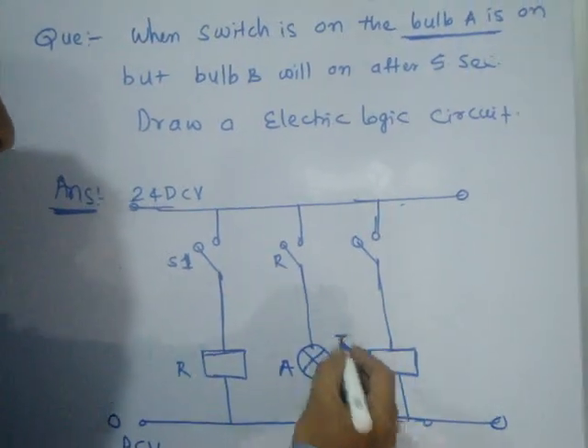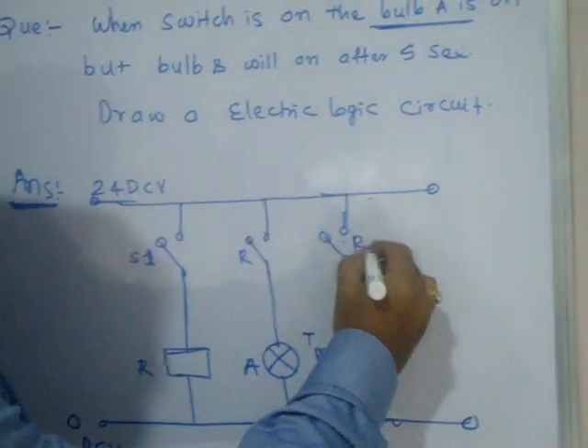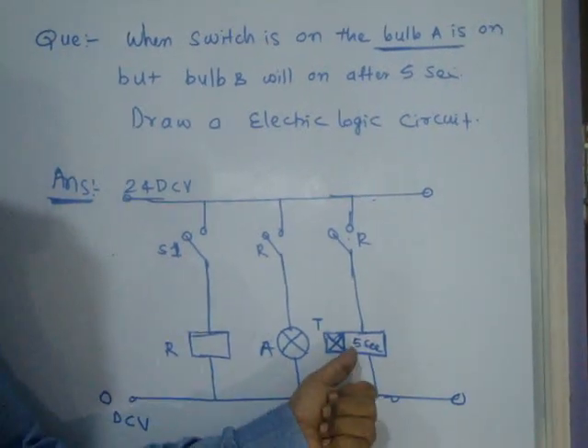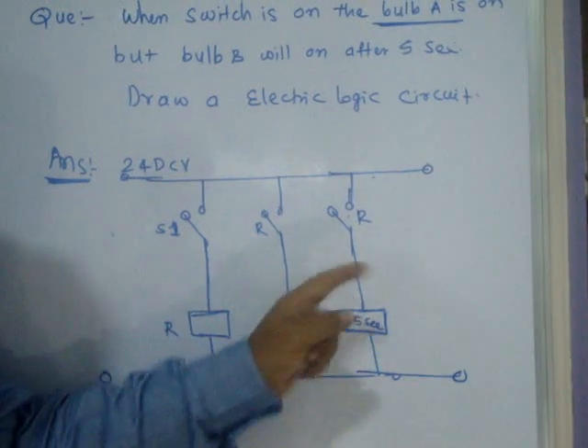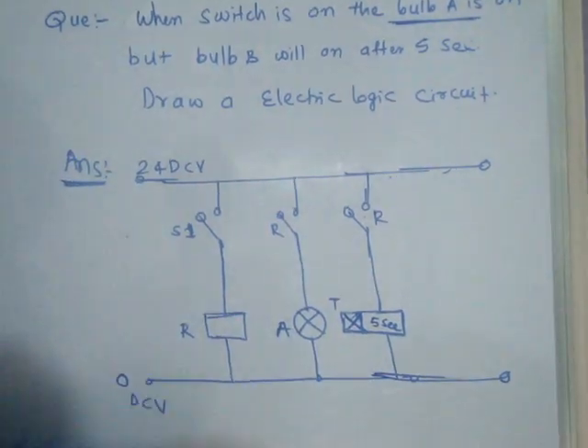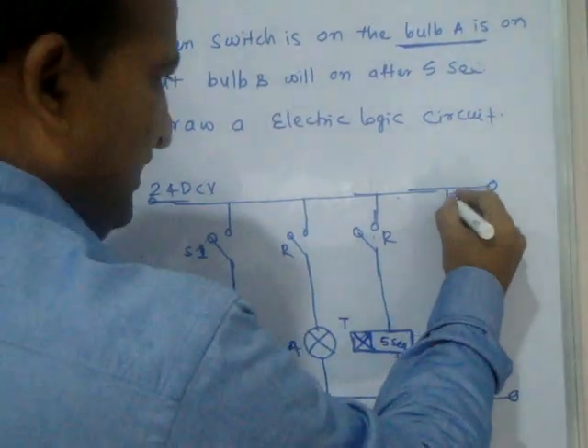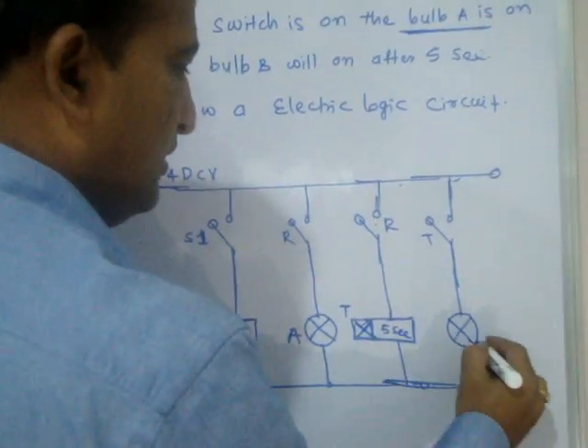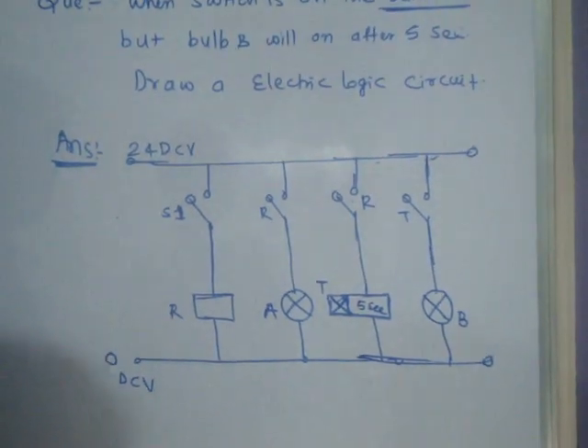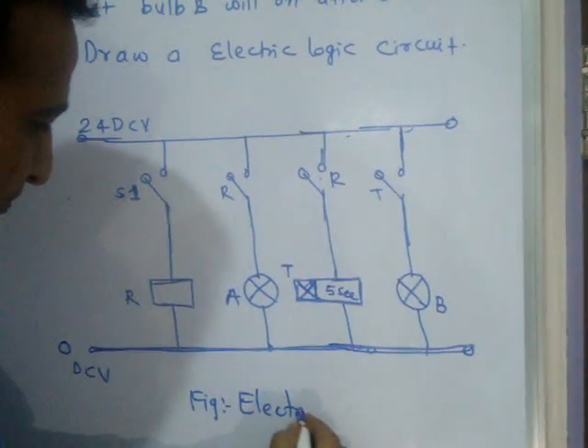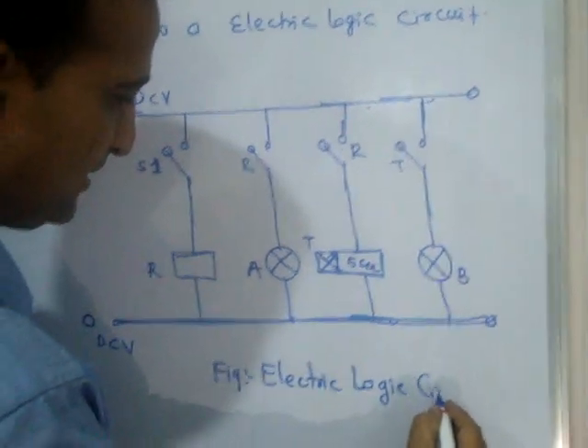When R closes, the timer starts. You will get the output of the timer after 5 seconds, because it is an on-delay timer. The preset time may be 10 seconds, 20 seconds — whatever you set. When the timer is on, T closes after 5 seconds, and then bulb B turns on. This is called an electric logic circuit.